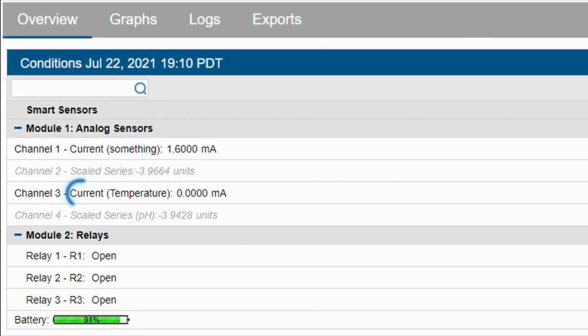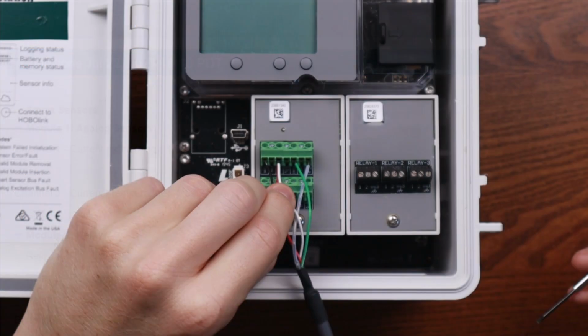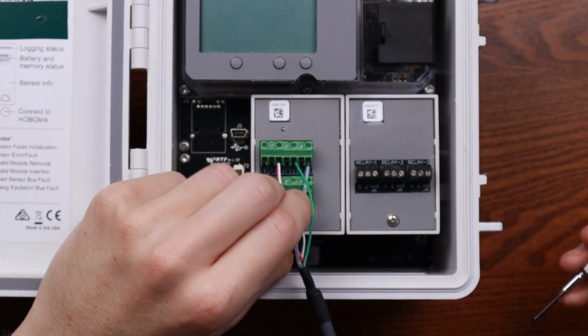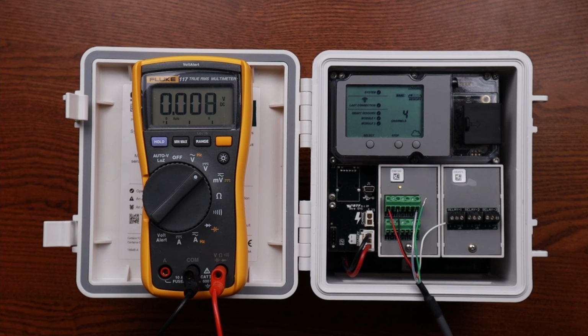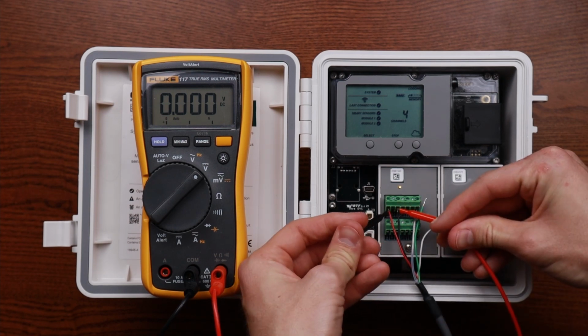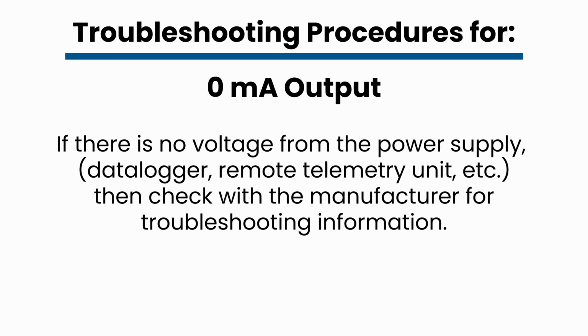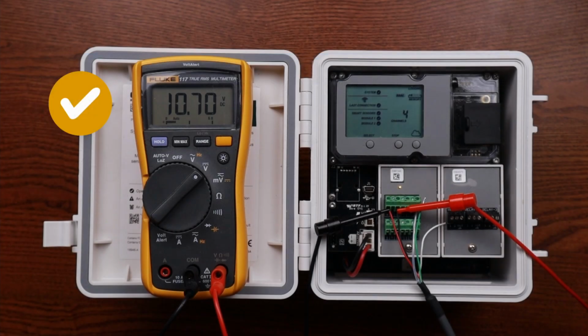A 0 milliamp output indicates the sensor is not receiving power. Start by double checking the wiring and cable. If all is fine there, then measure the voltage between a pair of wires when the power is turned on. If there is no voltage, then the power supply is not functioning properly, and we recommend checking with the manufacturer for troubleshooting information. If the voltage is steadily above 8 volts, but there is no output for the main parameter, then a connection is not being made inside the sensor.